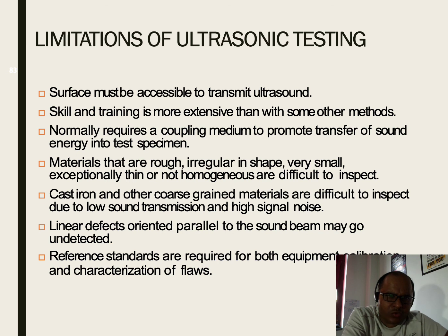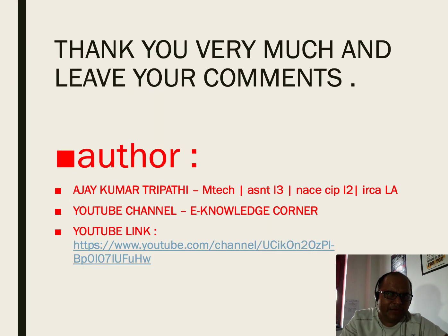Cast iron and other coarse grained materials are difficult to inspect due to low sound transmission and high signal noise. Linear defects oriented parallel to the sound beam may be undetectable, and reference standards are required for both equipment calibration and characterization of the flaw.